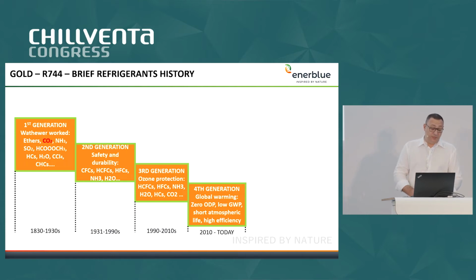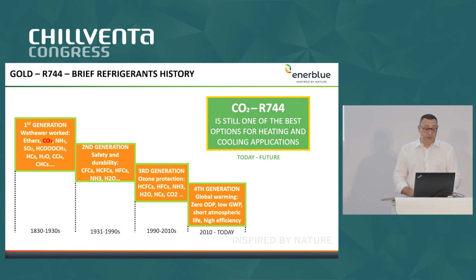Brief history of refrigerants. Starting from the first generation, we arrived at the fourth generation. So refrigerants with zero ODP, very low GWP, and short atmospheric life. But even if there are these chemical refrigerants, CO2 as a refrigerant, that is one of the first generation refrigerants, is still a good choice for heating and also for cooling applications.